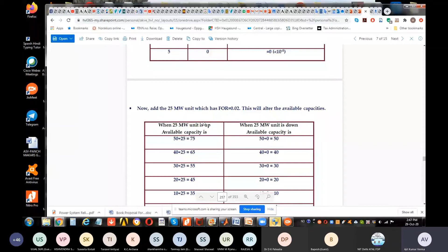So you have a consolidated COPT ranging from 75 to 0. We have used these two tables and combined them, 0 to 50 and 25 to 75. You insert all these values and then you get a consolidated COPT ranging from 0 to 75. Whenever you are adding, 25 plus 50, you take the probability for 50 multiplied by the probability for 25. Either it can be there or it cannot be there. So for 40, for example, it is not there, so you simply multiply by 0.02. Likewise for 25, if it is not there, it's 0. And then the cumulative probability goes from 0 to 1. Okay, so this is the cumulative COPT.